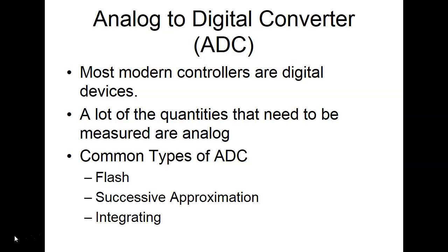And then that binary equivalent is going to mean something inside a computer program. So we have 3 types that we'll look at. The main one that we usually look at is this dual slope integrating amplifier. This is the one that's used most often. I mean, A to D converter. This is what your digital meter uses. This is what most PLCs use. We'll look at that one in a little more detail.